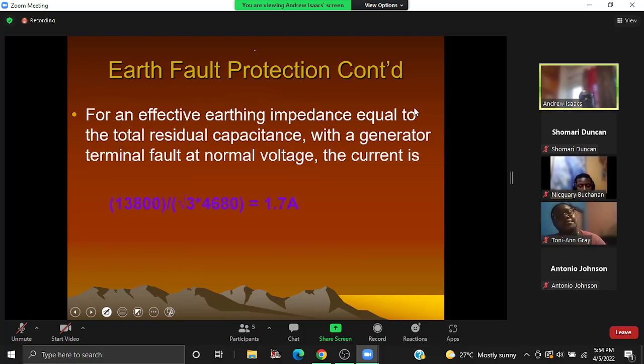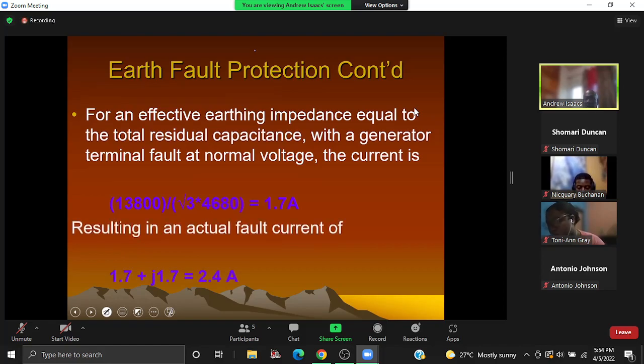So the corresponding current then would be 1.7, and that's the modulus, all right? Which means, therefore, that the actual fault current would be 1.7 plus j1.7. Remember, we didn't have a capacitance, so that would have been R minus jXL. Now, we are not using it as a complex number. What we are looking at is that you have a component going through the resistance and a component through the capacitance. Are you with me?